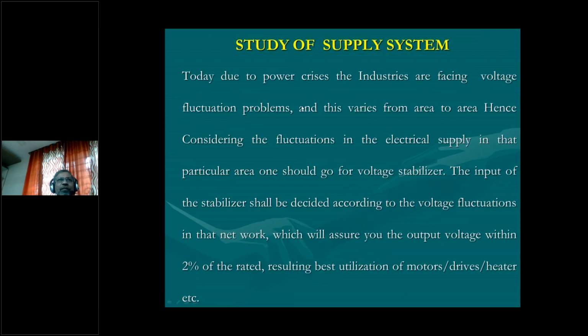Now, the study of the supply system. Today, due to the power crisis, industries are facing voltage fluctuation problems, and this varies from area to area. Hence, considering the fluctuations in the electrical supply in that particular area, one should go for voltage stabilizers. The input of the stabilizer shall be decided according to the voltage fluctuation in that network, which will assure you an output voltage within 2% of the rated. Of course, this is a study of supply. This is focusing on particular equipment or instrument or some machinery. If you have CNC machines, then the manufacturer will recommend that you provide stabilizers for that.